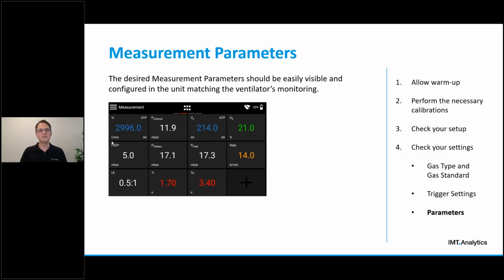So gas flow analyzers can typically measure up to or more than 25 different parameters. Further, they can usually display them in multiple different units of measurement. For example, pressure could typically be displayed in centimeters of water, millibar, PSI, or Pascal. Going through all of them would be a topic for a future education session, but it's important that you understand the capabilities and terminology used by your analyzer as well as your device under test in order to configure your measurement parameters on the analyzer appropriately, matching the compared values on your ventilator.